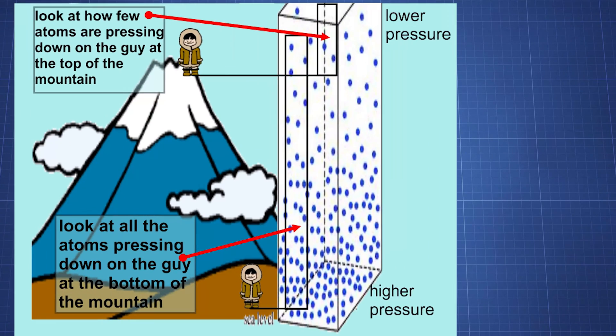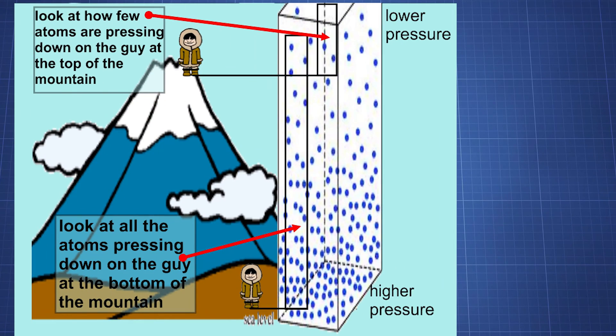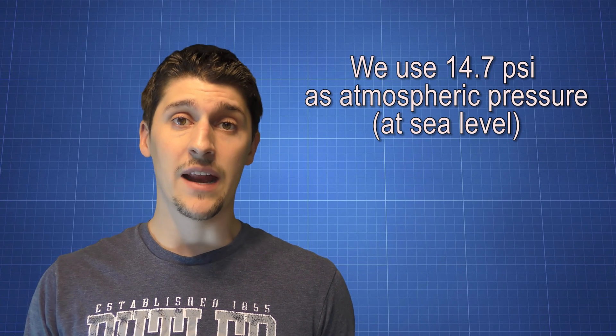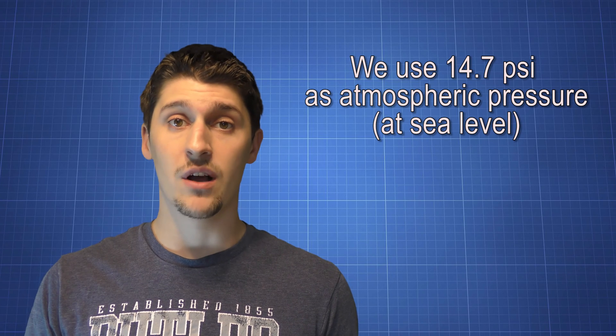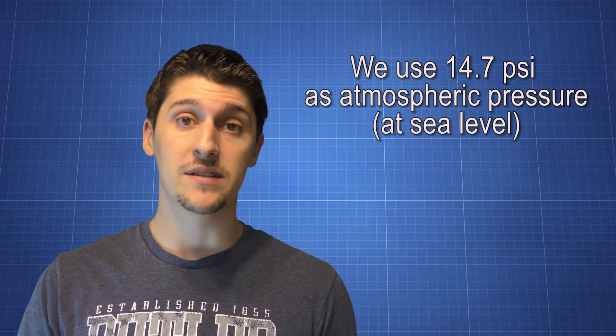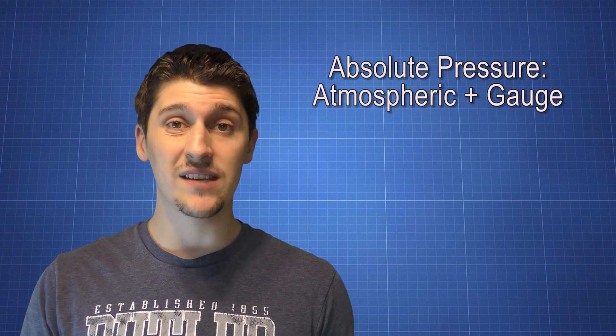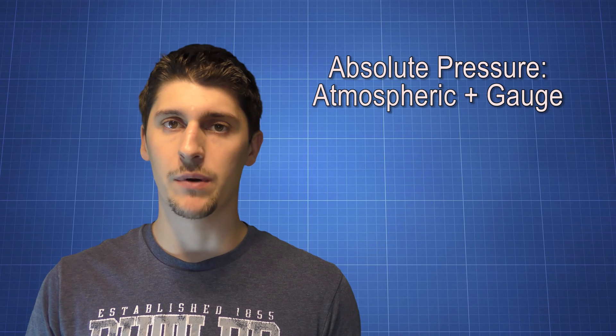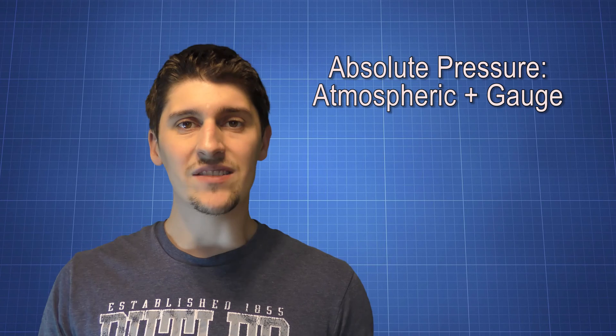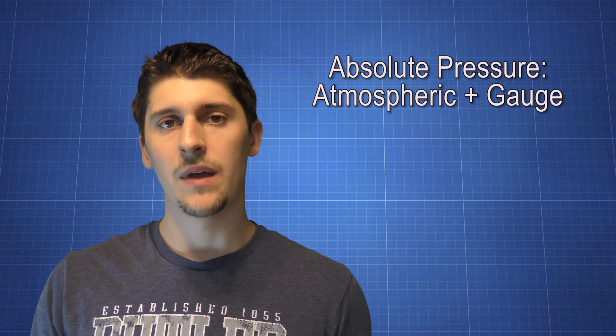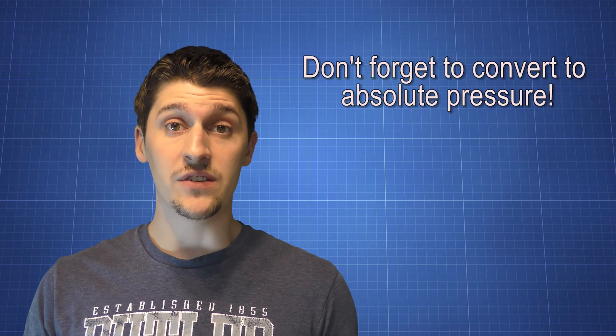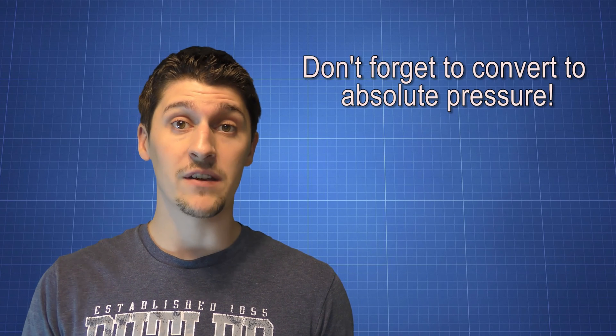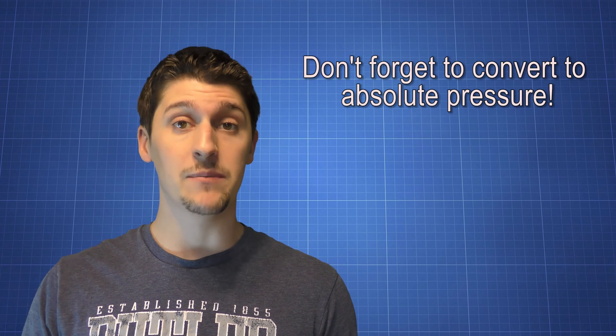Atmospheric pressure is the pressure that's being put on us by the air around us. At sea level, we all experience an atmospheric pressure of 14.7 PSI. Absolute pressure is gauge pressure plus atmospheric pressure. Inside of a system, atmospheric pressure isn't taken into consideration by the sensor or the gauge. So when we want to determine the actual pressure that something is experiencing, we have to add in the atmospheric pressure. For our calculations, it's really important that we always convert gauge pressures to absolute pressures.